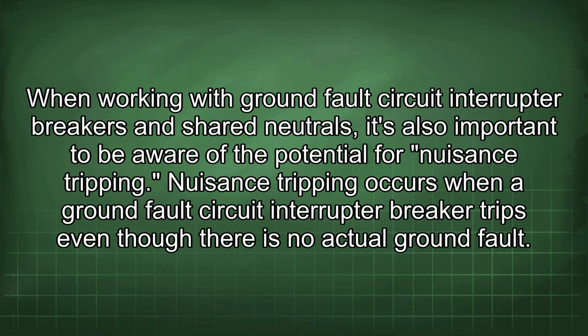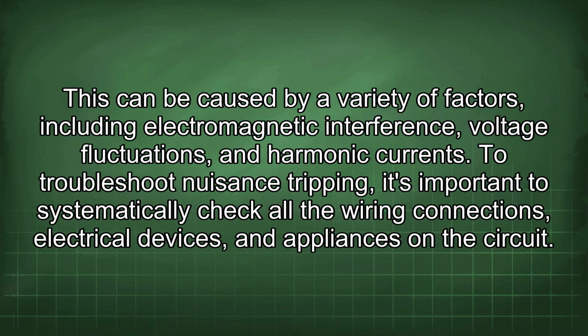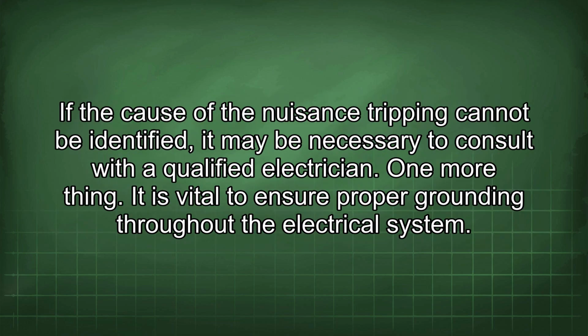When working with ground fault circuit interrupter breakers and shared neutrals, it's also important to be aware of the potential for nuisance tripping. Nuisance tripping occurs when a ground fault circuit interrupter breaker trips even though there is no actual ground fault. This can be caused by a variety of factors, including electromagnetic interference, voltage fluctuations, and harmonic currents. To troubleshoot nuisance tripping, it's important to systematically check all the wiring connections, electrical devices, and appliances on the circuit. If the cause of the nuisance tripping cannot be identified, it may be necessary to consult with a qualified electrician.